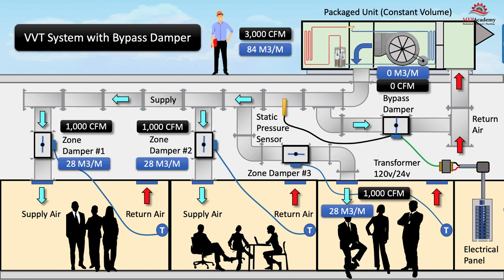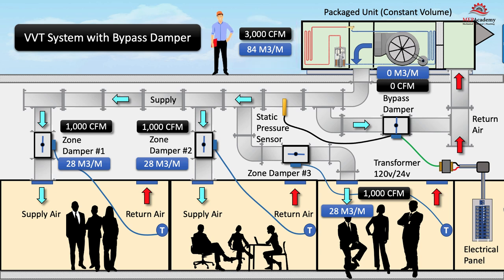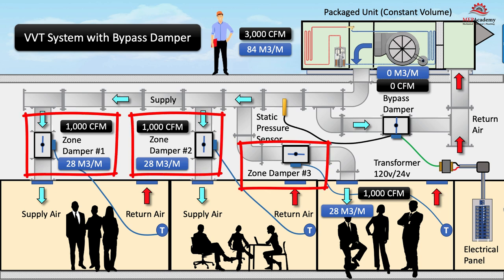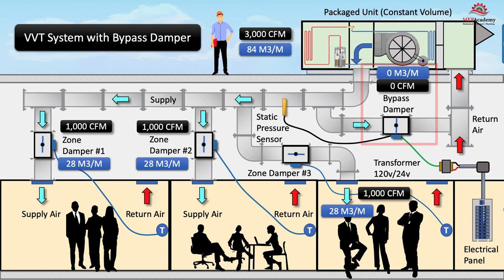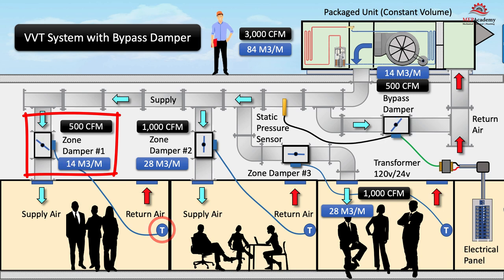Consider an example using a 3000 CFM (84 cubic meters per minute) constant volume air conditioner with three zones, each sized for 1000 CFM (28 cubic meters per minute) at peak load. The bypass damper is closed because all of the air conditioner's air is being delivered to the zones.